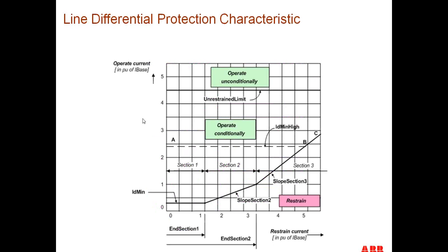So this is another picture of that same diagram we saw before, where we have a setting for the relay being ID min, which is the minimum differential current operate value that we have for the relay. This can be set anywhere from 0.2 upwards of 0.5 per unit of the base current of the relay. The base current is normally the size of the current transformer. So if you had a 1200 to 5 current transformer, then the setting would be in the area of anywhere from 200 amps to 600 amps for this minimum operate current. And then we have an end section 1 and end section 2, which, as we said before, you can leave fixed at 1 per unit and 3 per unit.